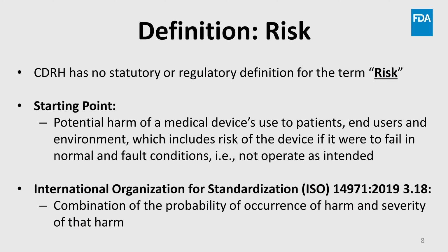My starting point, and again, these are my thoughts and not a formal definition. Risk is looking at the harm a medical device can cause the patients, end users, and their environment, which includes the harm if the medical device were to fail and not operate as intended in both normal and fault conditions. Also, understand we are not talking about financial risk. While I realize financial risk is important to manufacturers, for the purpose of this discussion and module, we will stay focused only on the risk of the medical device.